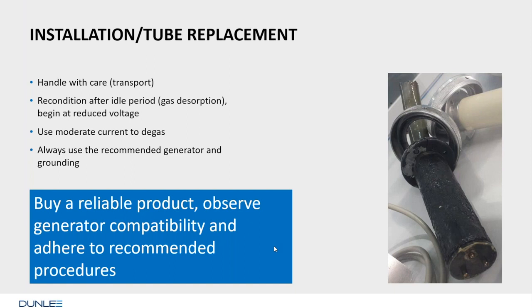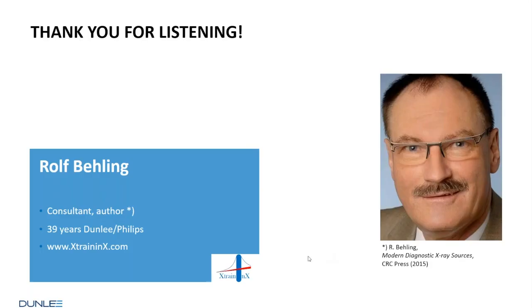What it means is that moderate voltage is applied, and a certain gas level is there, so that gas effects can also act on field emission centers. So the tube learns to live with all these circumstances and gets stable. And after warm-up, you can then raise the voltage carefully to the operational voltage.